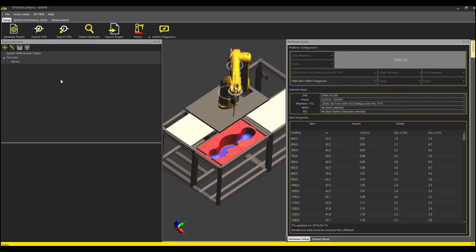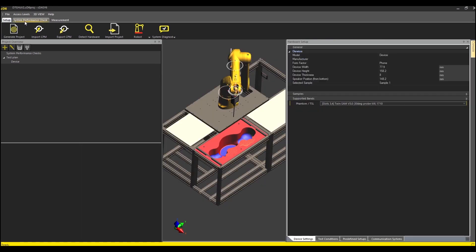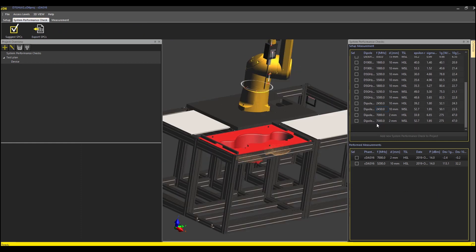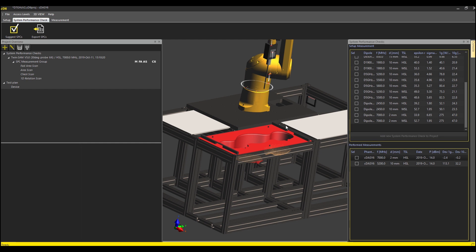Next, I click the system check tab and add the 7 GHz dipole HSL measurements to the project. The measurements are automatically added to the project with default area and zoom scan grid settings which are in line with the current standards.